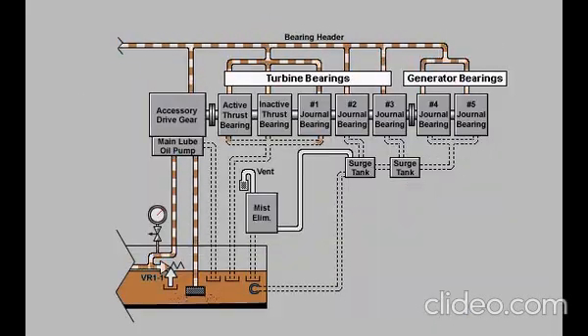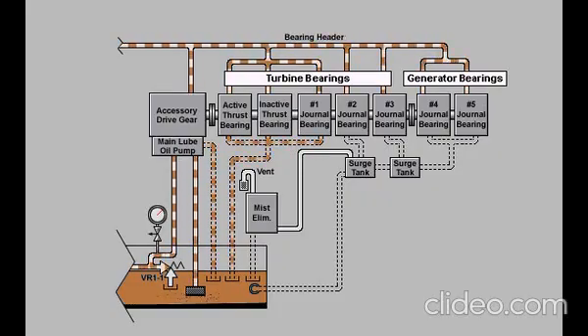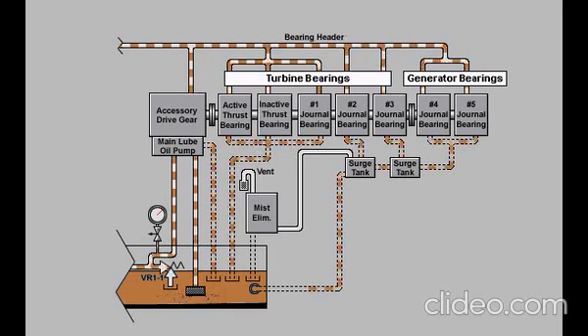After lubricating the accessory drive gear and the turbine number 1 bearing, lube oil drains directly back into the lube oil tank. Lubricating oil from turbine number 2 and number 3 bearings and from the generator bearings drains into surge tanks located in the turbine base. The forward surge tank drains into the lube oil tank.